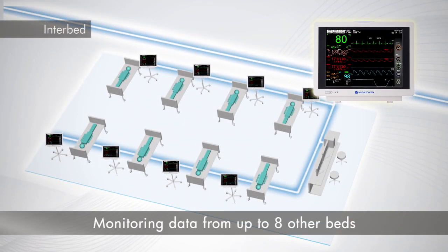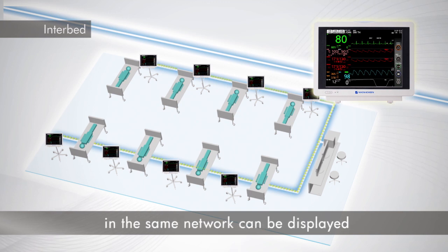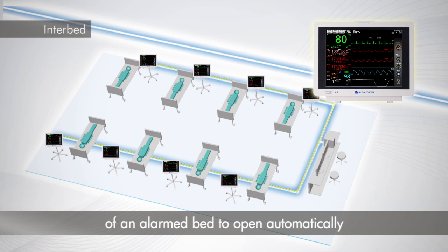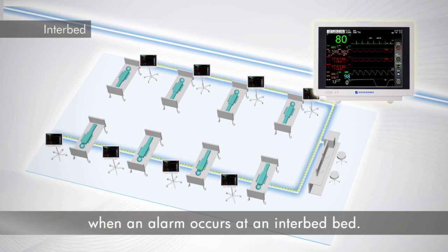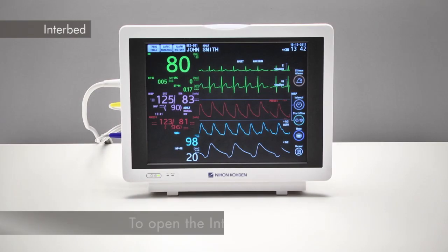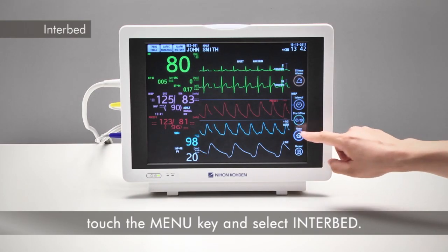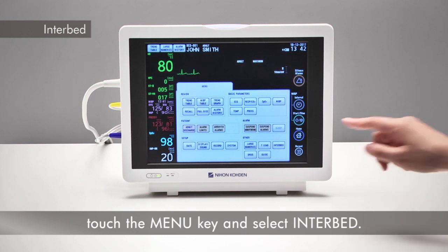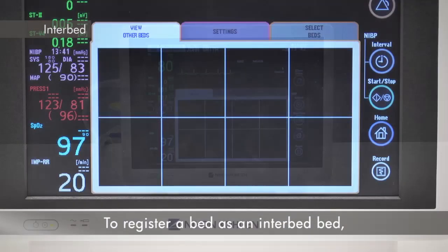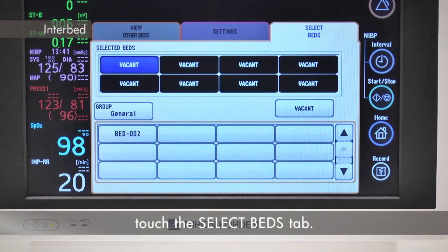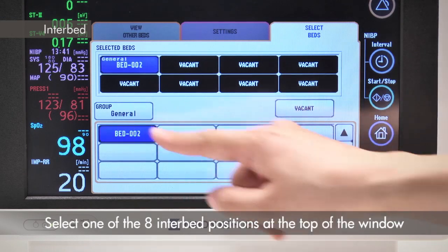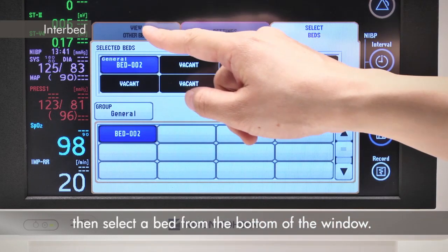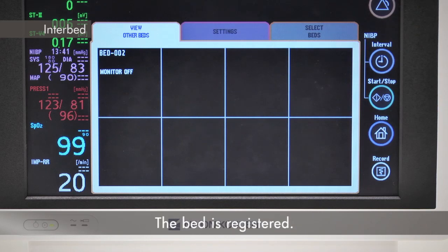Monitoring data from up to 8 other beds in the same network can be displayed on the Interbed window. You can also set the Interbed window of an alarmed bed to open automatically when an alarm occurs at an interbed bed. To open the Interbed window, touch the menu key and select Interbed. To register a bed as an interbed bed, touch the Select Beds tab. Select one of the 8 interbed positions at the top of the window, then select a bed from the bottom of the window. The bed is registered.